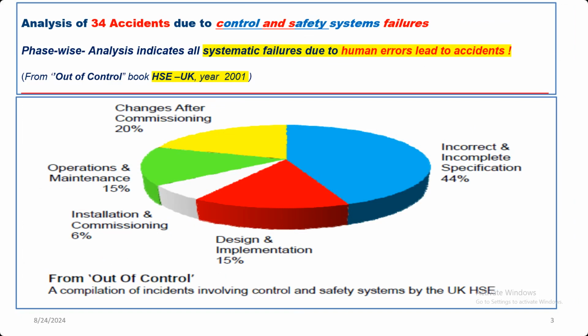So if you are specifying a wrong transmitter, with the wrong material of construction that is going to come in contact with the process fluid, probably even your SIL 3 transmitter will fail in a day. It will not take more than a day to live its life. So that is why complete and correct specification is a must, considering its application, and that is to be decided by the people who are building the plant, who know their process and what to select and not.